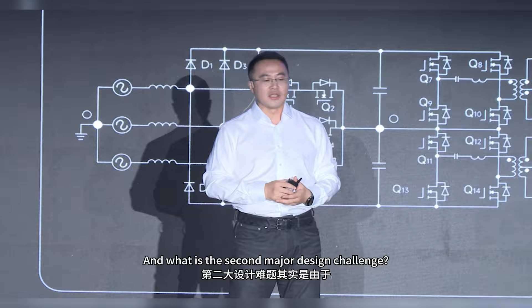Once the power level rises past 40 kilowatt products, you realize that many of the design methods and protection methods that worked at lower power might only fail after 3 to 5 years. But once you move to 60 kilowatts and above, because wind speed and air pressure rise so much, problems that once showed up after 3 to 5 years can now show up in around 1 year. Over the past 3 years we have really seen that the high incidence point for issues is around the 1 year mark. At that time it was extremely painful for us, because that product design had already been completed 1 year earlier. Where do the stress limits appear when a high power module scales up?